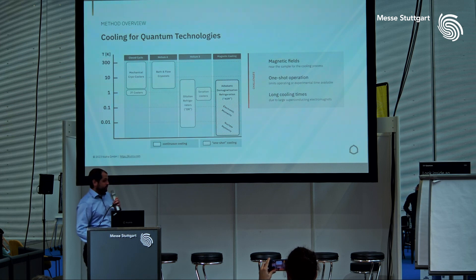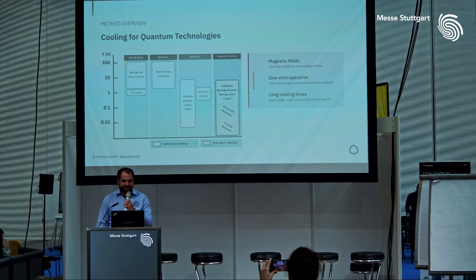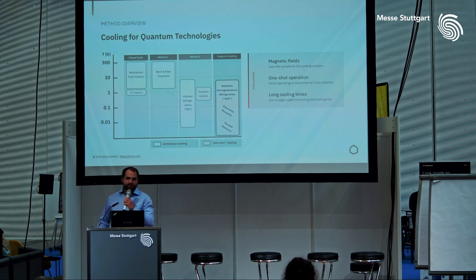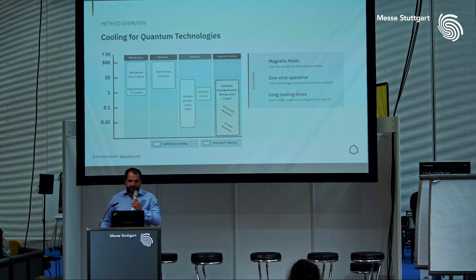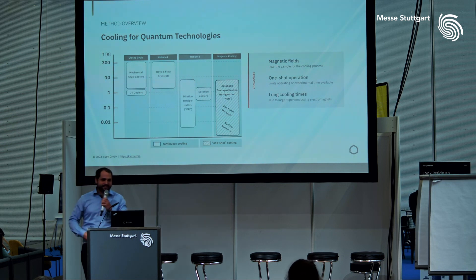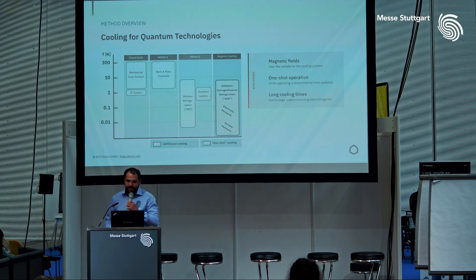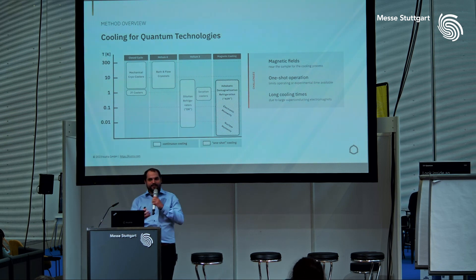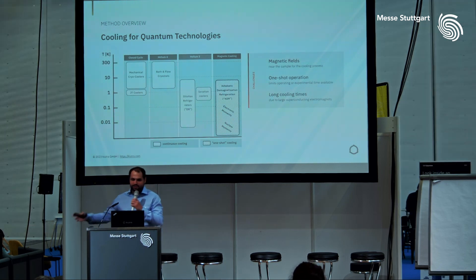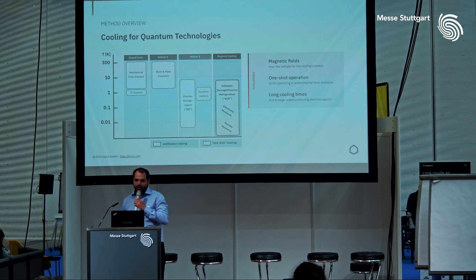The use of ADR — not a very new technology, it's been around since the 1960s — has been limited due to some challenges in its implementation. First, in traditional implementations of ADR, high magnetic fields are used, and the stray magnetic fields near the sample position are not compatible with most quantum technologies.